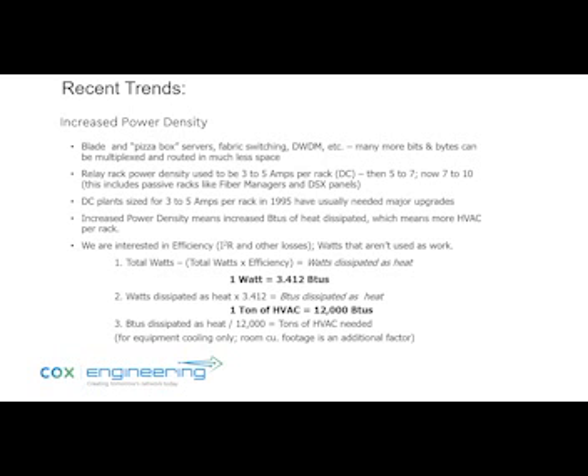So increased power density is something that we have seen over the years. We used to look at maybe 1 or 2 kilowatts per rack, but it's getting more towards 5 to 10 kilowatts per rack, depending on what's being done within the rack, whether there's a lot of cloud compute or things like that. So the things that are cool to know in terms of just handy little calculations is BTUs, basically.